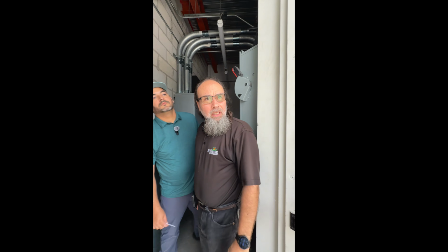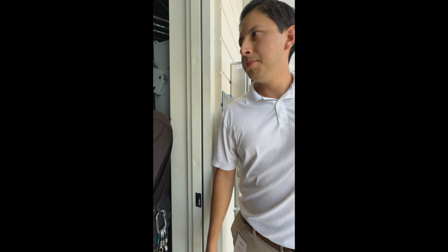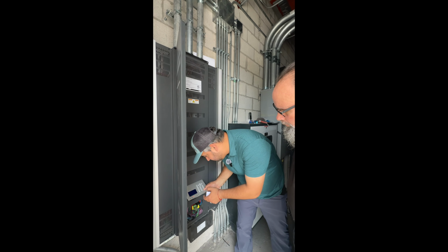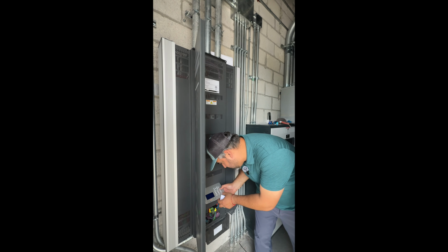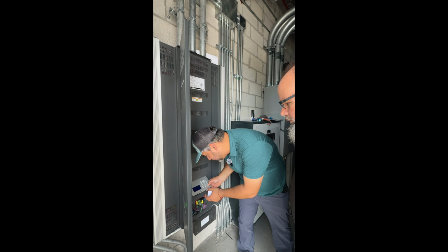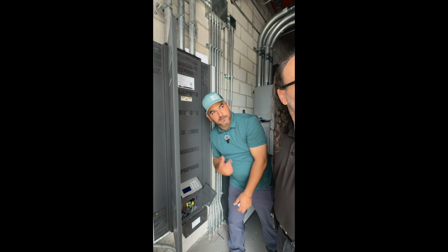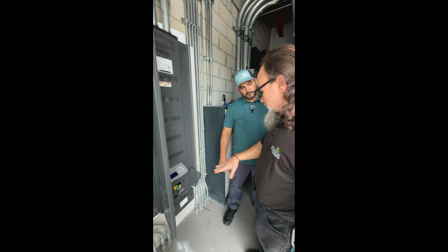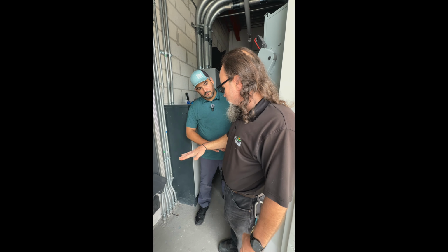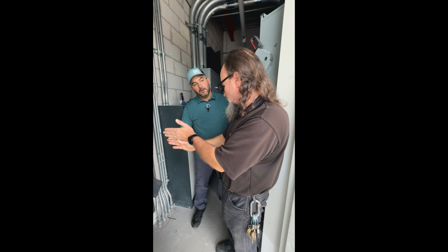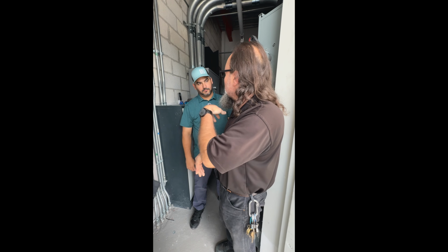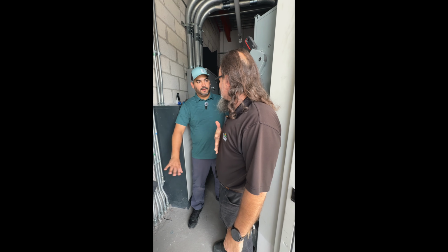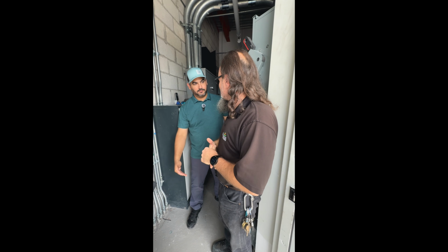These lights are currently on right now. Is that what it's saying? Yeah, we're overriding. So if we go back, hit enter, operation, output override, all output 0. So that override is there, but it's temporary. As soon as it gets the next command, either dusk or dawn, it's going to execute every time, because we don't have priorities. Everything is whoever comes next.